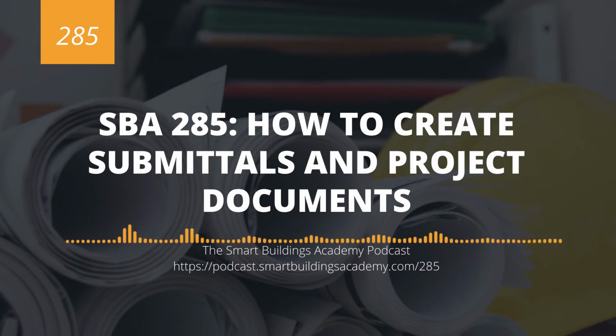Now, this is all detailed typically in section 1 of your division specification. That's the general section, and about halfway down the general section, there will be submittal document requirements. It'll typically say how many submittals are required, what form they need to be in, what information they need to include, when they need to be submitted, and any project dependencies that rely on submittal approval. For example, you can't order material or execute labor or do your first billing until submittals are approved.